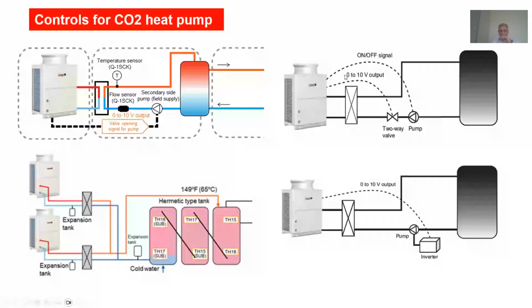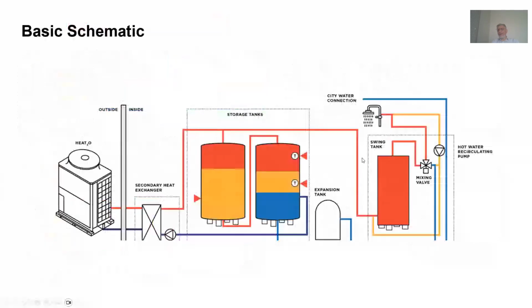So to vary the flow, you have got two options. You can go with a constant volume pump with a two-way valve that would operate and make sure that you maintain a certain amount of flow on the primary secondary side, or you can have an inverter-based pump that would modulate depending on what temperature is sensed by the secondary sensors.